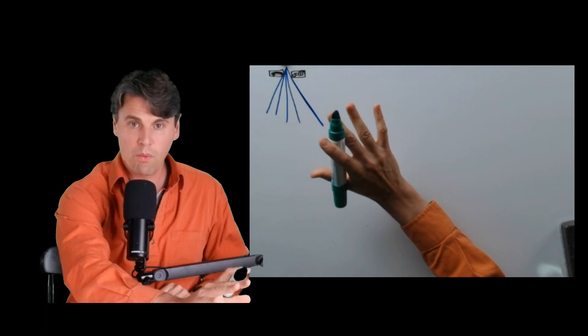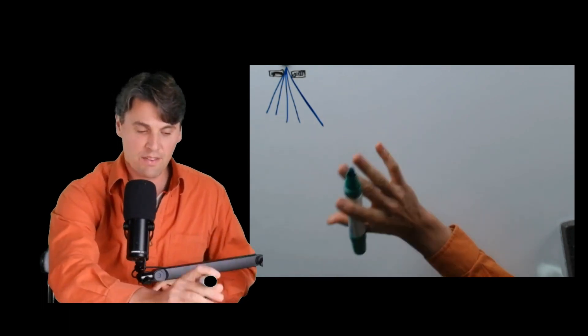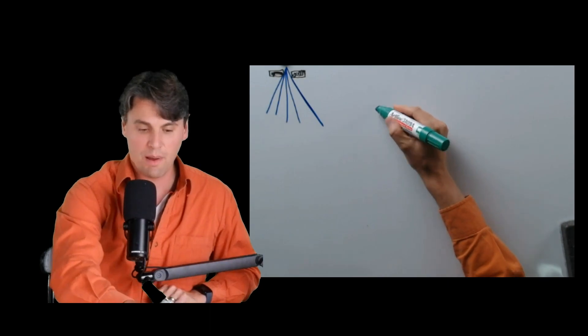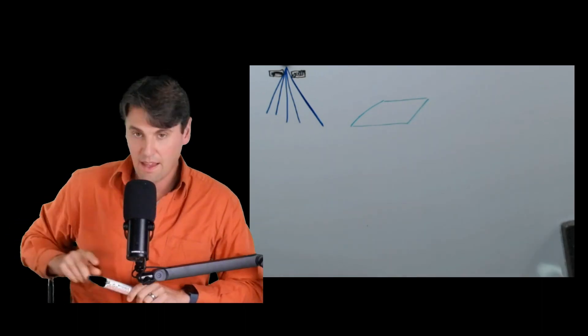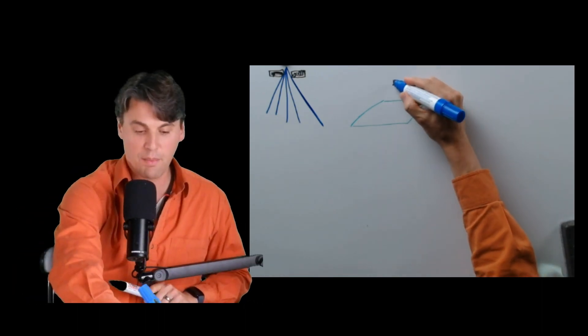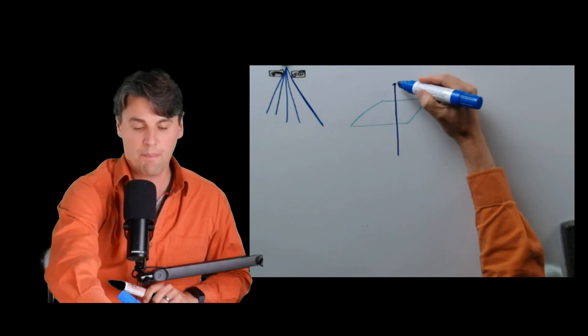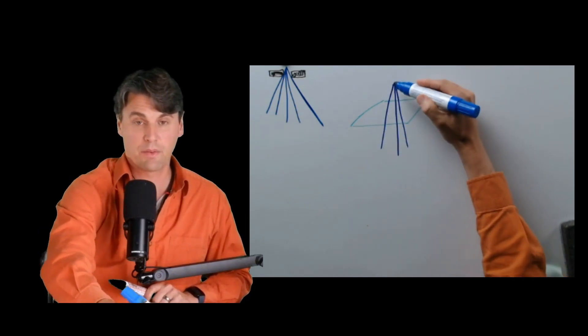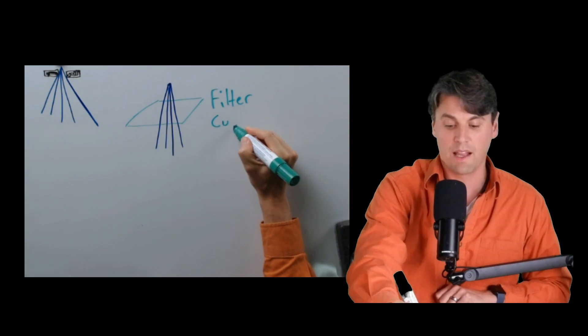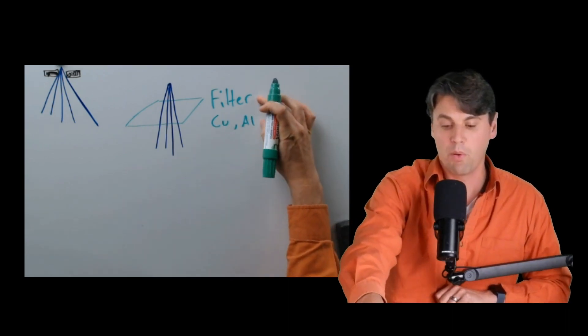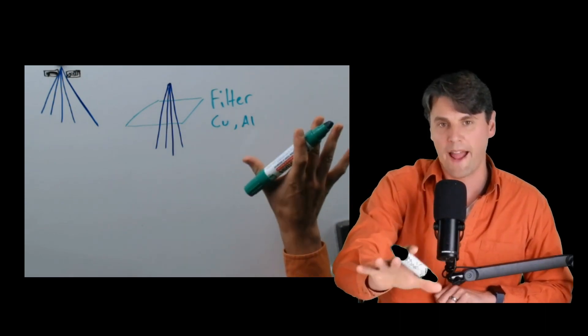You have millions of x-rays coming in for every acquisition within every detector pixel. In the simplest case for x-ray imaging, we can think about using a thin sheet of metal. The x-rays pass through that metal either before or after the collimator, uniformly passing through it. This is what we call a filter — it could be copper or aluminum — and this filter is going to do something called harden our x-ray beam.